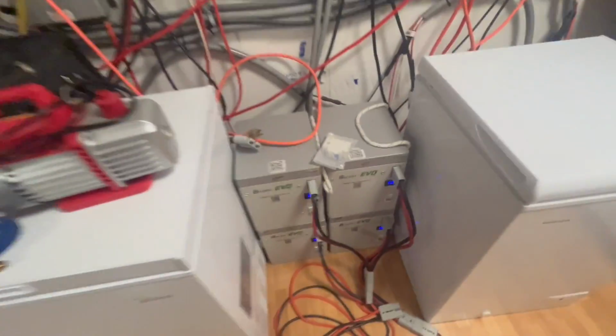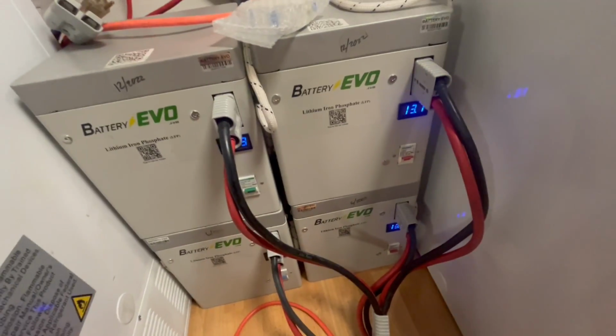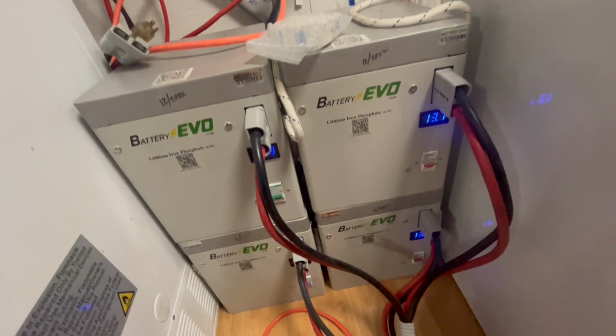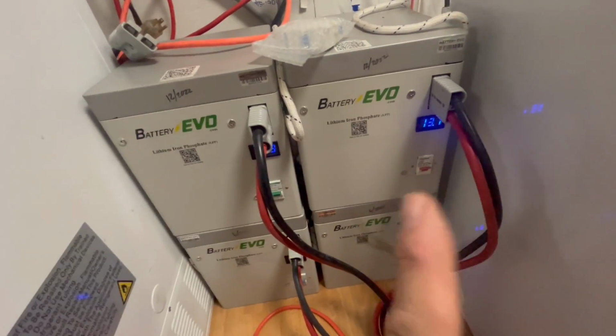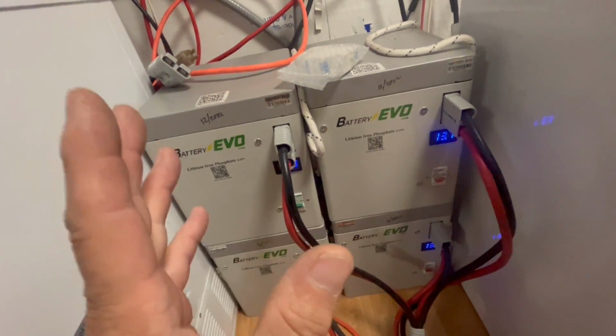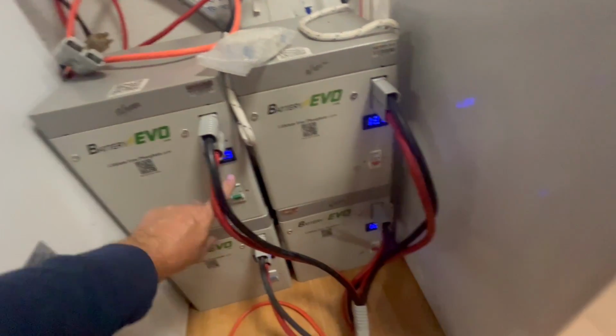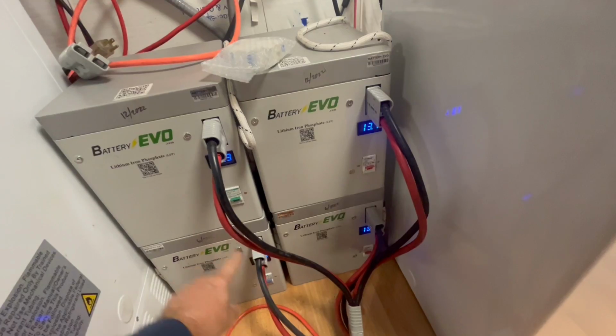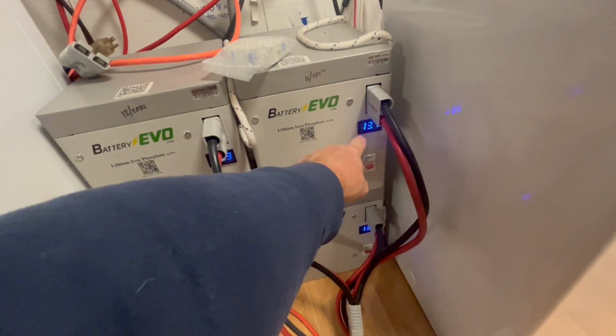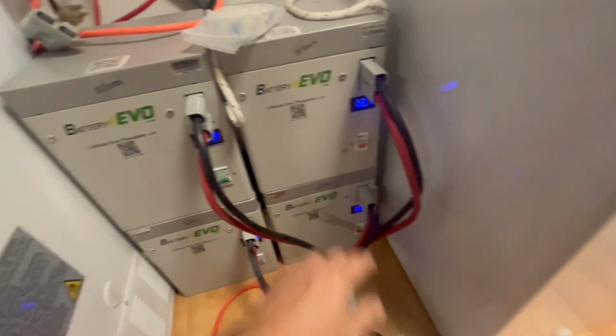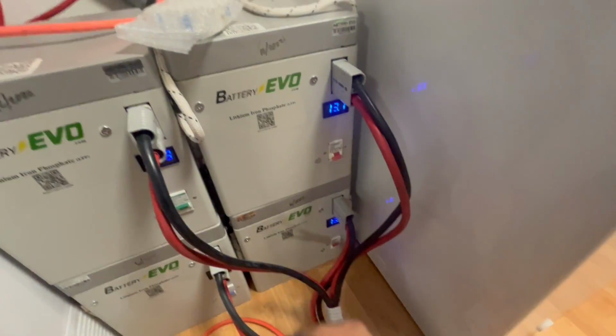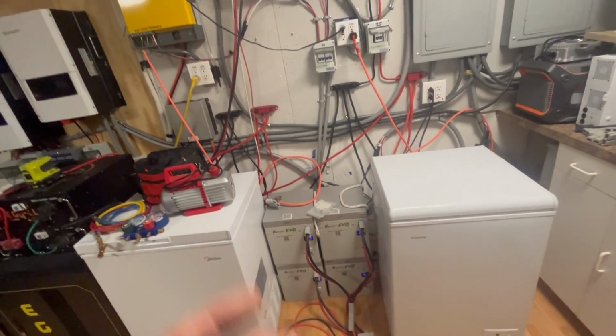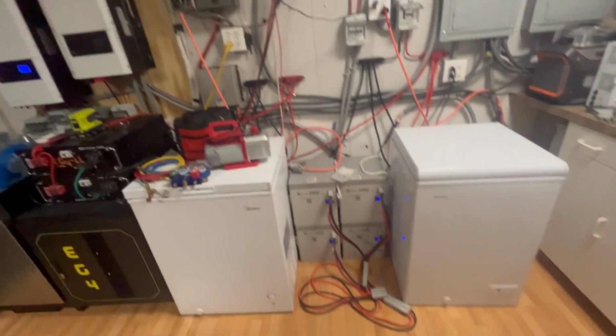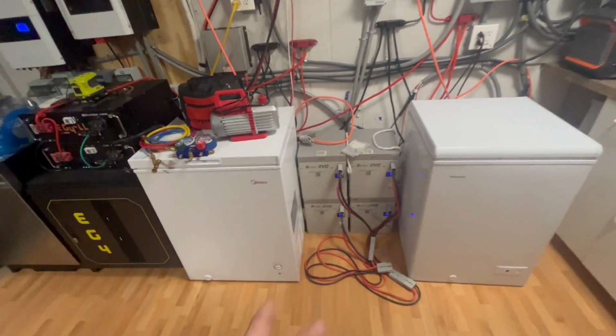The other day I was running this mini split. These are rated to go down to 10.5 volts each, and when one of these batteries drops to 10.5 volts, it cuts them all and shuts down your inverter. So you could have 12 volts, 12 volts, 12 volts, and this one gets down to 10.4 volts, and it'll shut this one down—the breaker will trip, and it shuts everything down. You no longer have 48 volts, you have 36 volts, and that'll shut down your inverter. So you can't even get to that 10.5 volts.